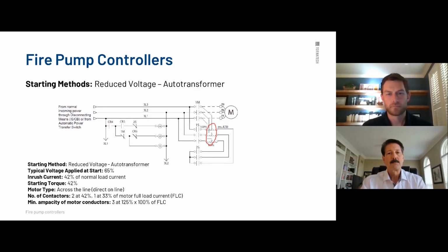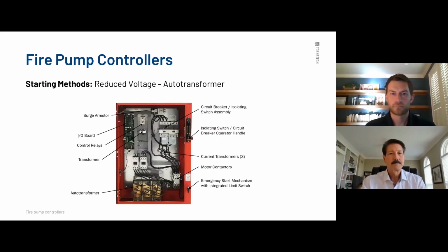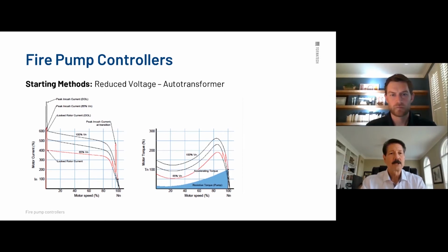And then as we ramp up, what will happen is, as you'll see briefly here, we have an inrush close to peaking 3 to 4 times full load amperage. Again, this high inrush here is almost negligible, the peak inrush. But as you see, as speed increases here, the RPM, amperage drops down. We do have a slight peak right here because the speed goes up and we're transitioning from 65% to full voltage, so we'll pick a little spike up there that's very minimal, but it really is a nice transition. So auto transformer has been used for a lot of years. Again, it's been a steady eddy in the industry for a while, but is being displaced by soft starts.